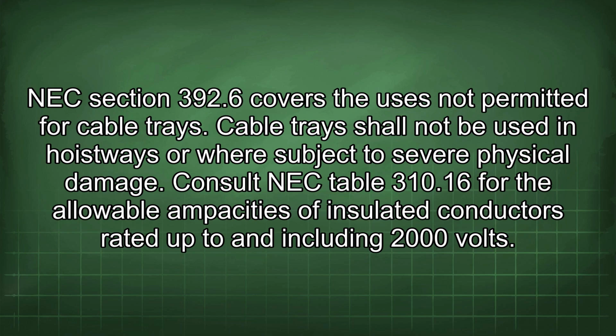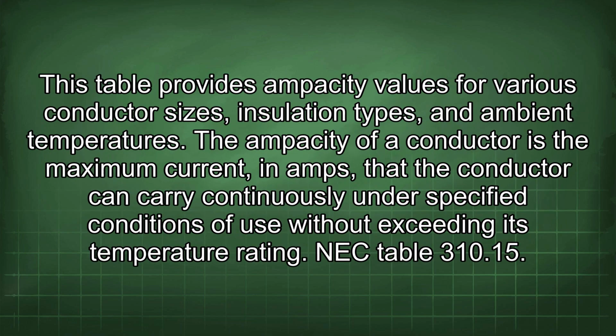Consult NEC Table 310.16 for the allowable ampacities of insulated conductors rated up to and including 2000 volts. This table provides ampacity values for various conductor sizes, insulation types, and ambient temperatures. The ampacity of a conductor is the maximum current, in amps, that the conductor can carry continuously under specified conditions of use without exceeding its temperature rating.